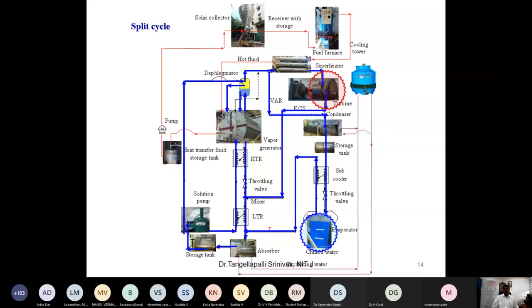So all these four versions have been practiced in the experimental laboratory, using the Kalina cycle power plant and also the vapor absorption refrigeration system. We are calling it a single plant. It's not two plants. It's a single plant system only. In this single plant system, since the working fluid is aqua ammonia, a binary fluid system, we should not go for copper or copper family materials like bronze, because we can't use ammonia with copper or related metals. So iron or steel can be used. We use high grade steel, since it is a chemical related plant.